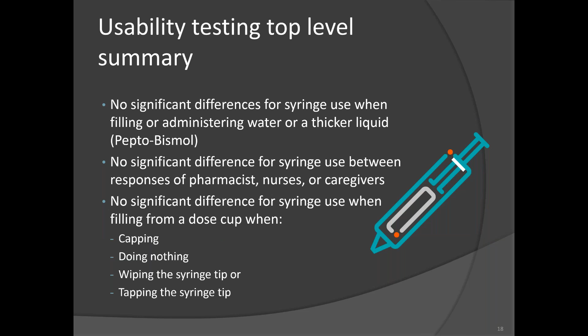To conclude, on some of the concerns that you might have heard about, performance testing results showed that the low-dose tip was delivering an accurate dose, negative 2.9% to positive 10.47%, with a 95% confidence interval. We found this to be substantially equivalent to standard orientation enteral syringes and to perform better than other reverse systems out there. We've also found in our studies that use of an adapter, such as a straw, provides even better performance than a cup fill. And so if you're looking for dose accuracy that's even better than 10 or 9%, then you should use a drop straw or some type of medication bottle adapter.